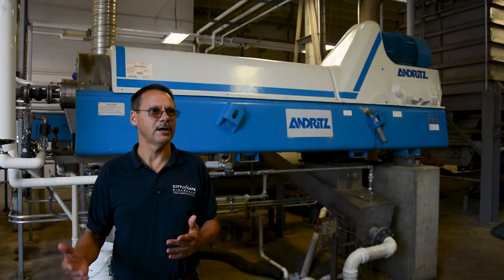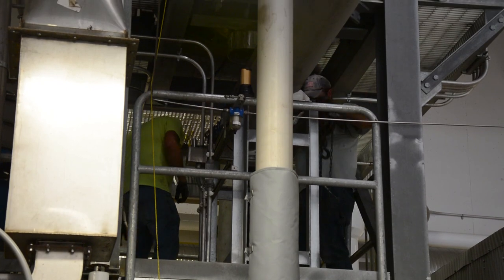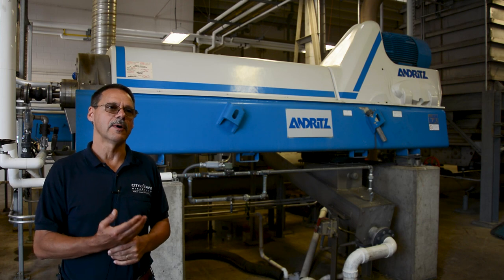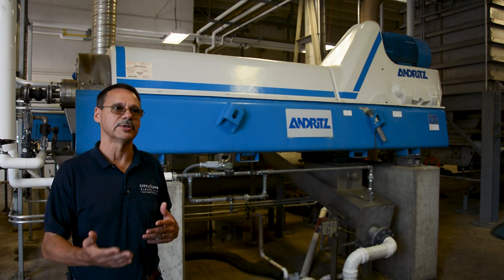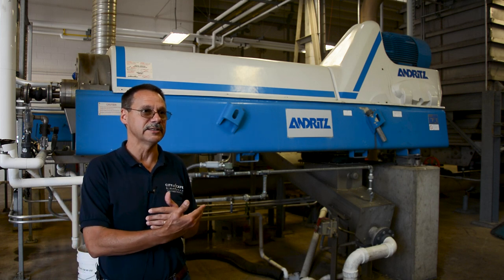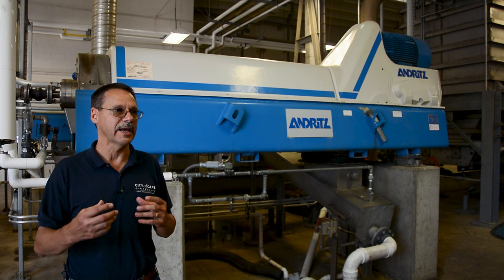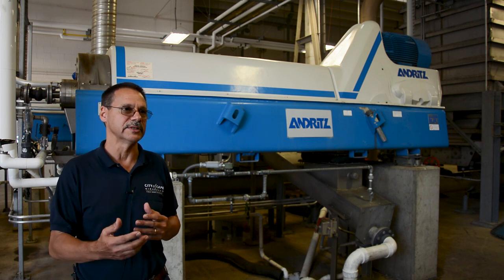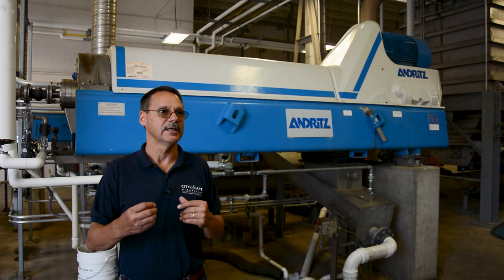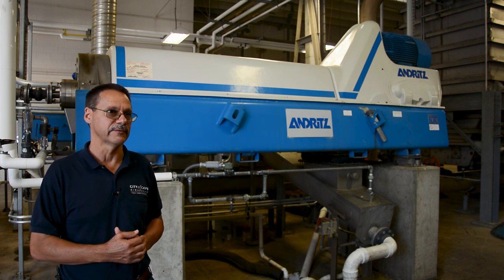We're now down in the biosolids building, and this machine behind me is a centrifuge. We feed that waste activated sludge we just saw into this machine at about 100 gallons a minute, and we are creating a paste referred to as 'cake' in this industry — it is around 24% solids. That material is then fed into our biosolids dryer to create the fertilizer.